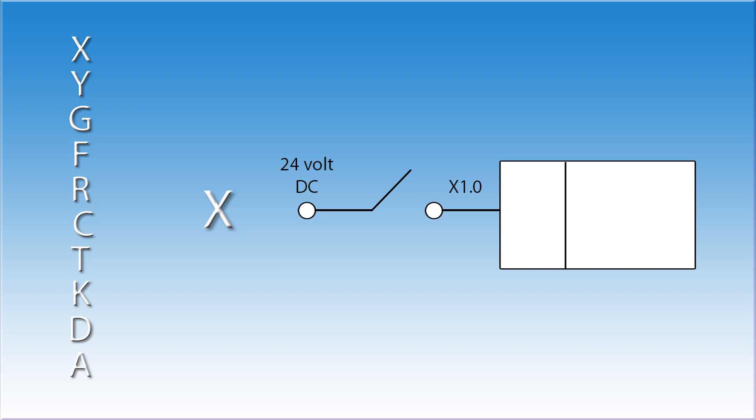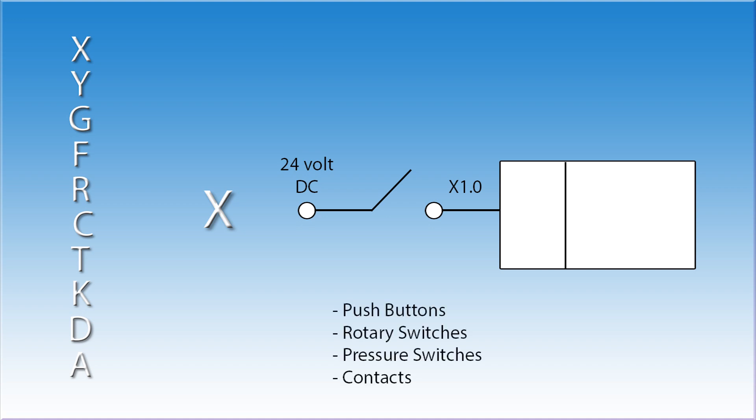The machine tool builder is responsible for wiring up all X value inputs. These can be items such as push buttons, rotary switches, pressure switches, or contacts. Since the X addresses are inputs, they can only be used as contacts in the ladder. You will not find them used as coils. If you are familiar with the Allen-Bradley control, they refer to these as I signals.